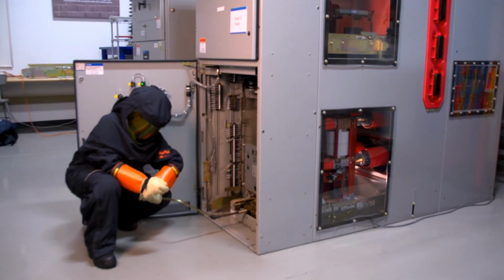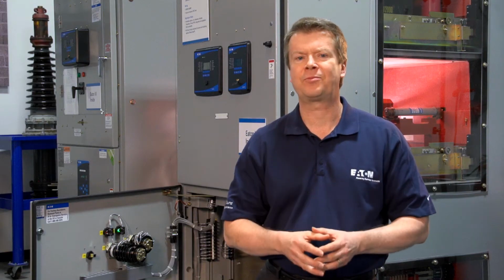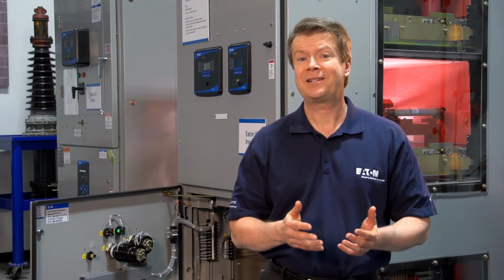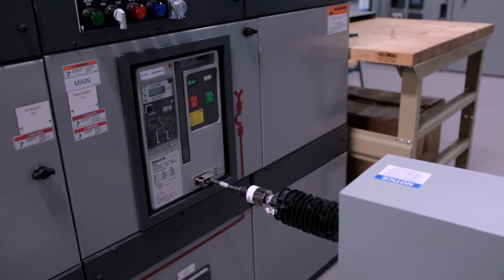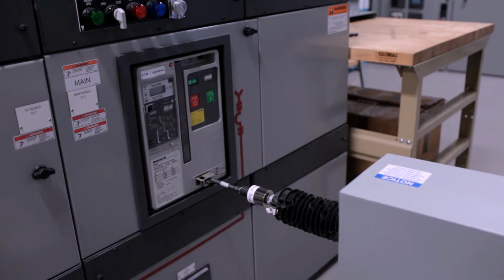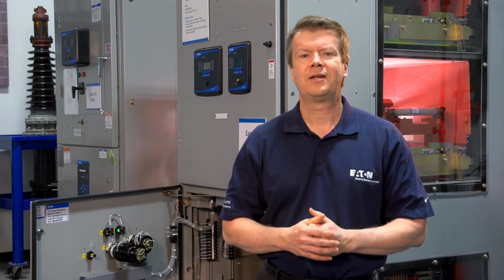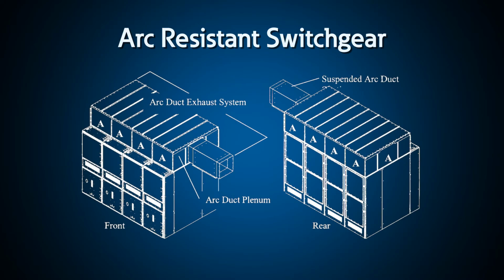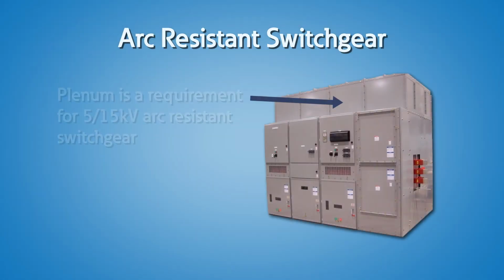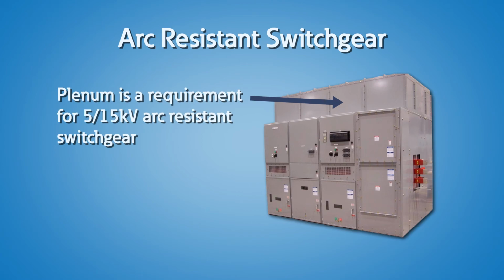Arc flash events may occur when you're racking in or out a circuit breaker. Using a robotic device like the RPR2 can keep personnel at a safe distance in case an arc flash event would occur. Medium voltage and low voltage arc resistant switchgear uses a plenum or chimney to vent away an arc flash event if it were to occur.